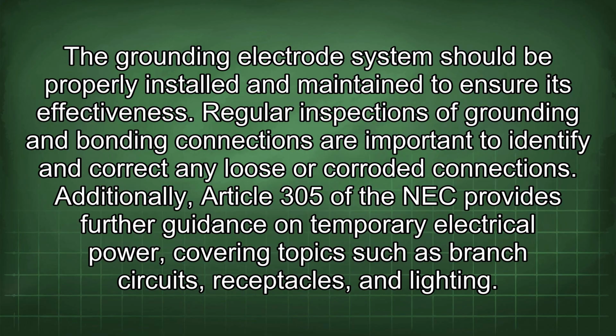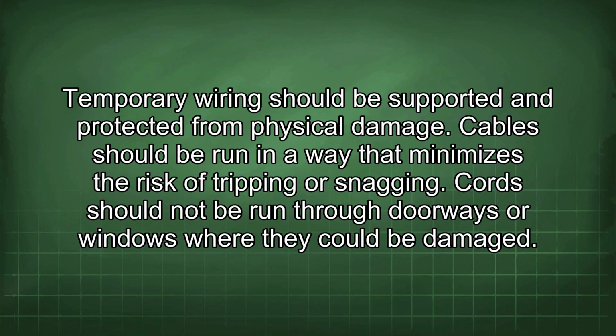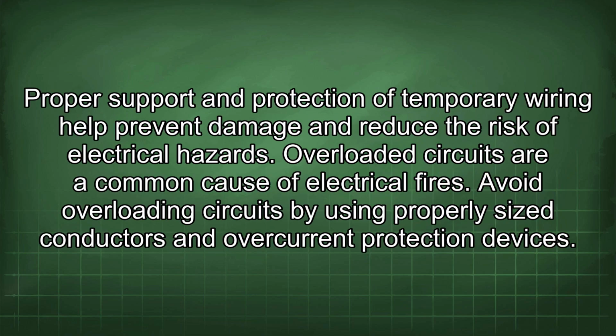Additionally, Article 305 of the NEC provides further guidance on temporary electrical power, covering topics such as branch circuits, receptacles, and lighting. Temporary wiring should be supported and protected from physical damage. Cables should be run in a way that minimizes the risk of tripping or snagging. Cords should not be run through doorways or windows where they could be damaged. Proper support and protection of temporary wiring help prevent damage and reduce the risk of electrical hazards.